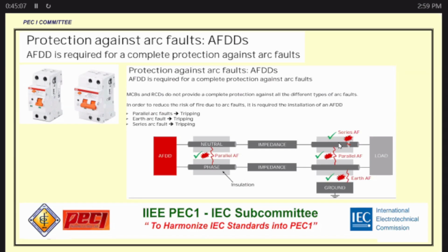If we have any of those classified arc faults, this device would sense it and could arrest it in order to reduce the risk of fire due to arc fault. So the cause of our fires, if we look at it, it's not really short circuit, not really overloading. We know, for our friends in informal settler areas, arc fault is always small, you can't really detect it. That's why they say, if not in use, turn it off. But when you forget, even in our convenience stores that get burned, we hear about it. Burned due to aircon, due to their freezer, that's where the arc fault happens. So if that's not arrested, you get burned. Imagine, your investment in protection is so small, but if you get burned, everything is gone. Everything. Better to get robbed than to get burned. That's why we need protection.